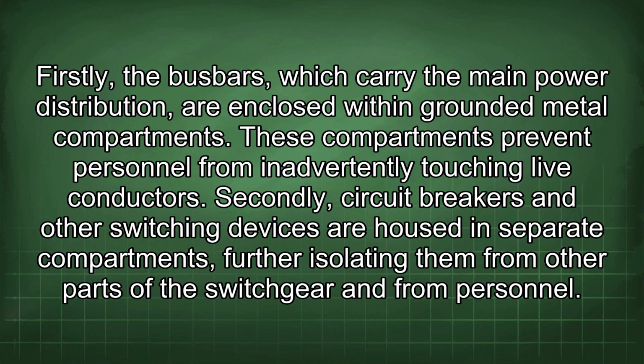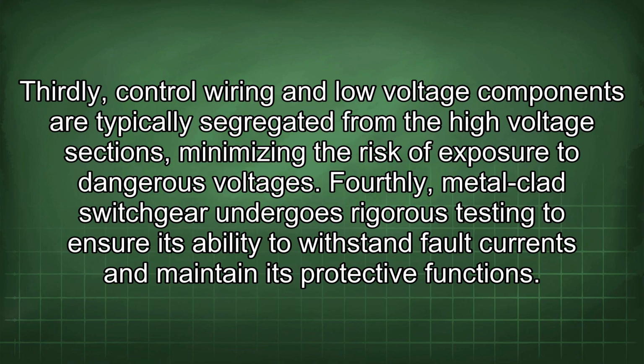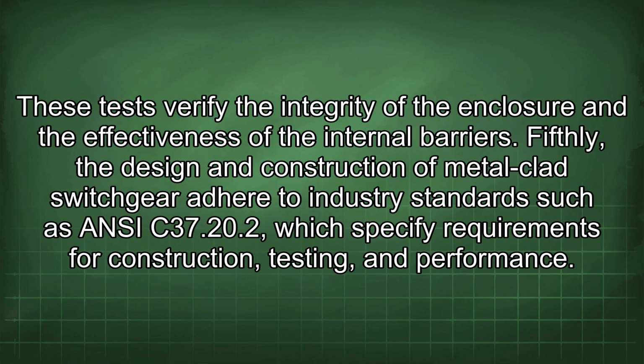Secondly, circuit breakers and other switching devices are housed in separate compartments, further isolating them from other parts of the switchgear and from personnel. Thirdly, control wiring and low-voltage components are typically segregated from the high-voltage sections, minimizing the risk of exposure to dangerous voltages. Fourthly, metal-clad switchgear undergoes rigorous testing to ensure its ability to withstand fault currents and maintain its protective functions. These tests verify the integrity of the enclosure and the effectiveness of the internal barriers.